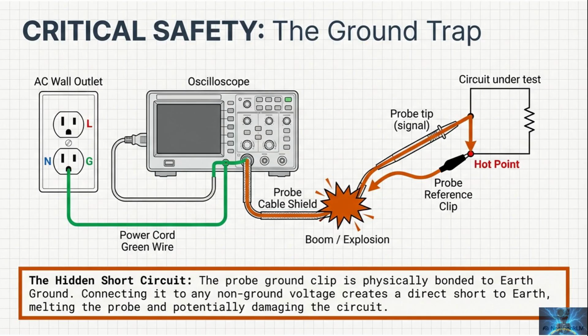Critical safety, the ground trap. This is one of the most important lessons in oscilloscope life. The probe's ground clip is tied to earth ground through the scope's power cord ground. That means if you clip the probe ground to a hot point that isn't earth ground, you can create a direct short to ground. Sparks, damaged probe, damaged circuit, maybe worse. The rule: treat the probe ground clip like it's a hard connection to earth ground, because it is.